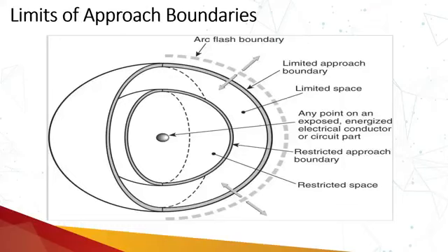Basically, we have seen that in order to receive a shock, you don't necessarily need to touch the conductors themselves. If you are in such close proximity that there is a chance of an electric arc-over phenomenon, we have to keep ourselves at a safe distance so that we are not electrocuted. That mandatory clearance is basically the restricted approach boundary. The restricted approach boundary is the trigger point for the qualified person: they cannot enter this boundary until and unless they are wearing proper shock protection personal protective equipment.